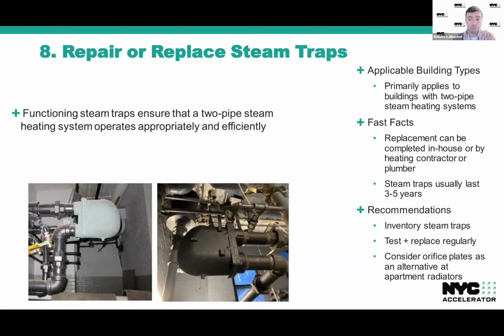This is going to primarily apply to buildings with two-pipe steam heating systems because those have by far the most steam traps. A lot of replacement work can often be done in-house by qualified or competent building staff. Other times, a heating contractor or a plumber is going to be the one who comes in to do this work. Steam traps wear and tear and they break down. A typical steam trap lifetime is approximately 3 to 5 years, which is why it's really important as a general recommendation to inventory steam traps, know where all of the steam traps in the building are, and have a protocol for testing and replacing any broken traps regularly. So staying on top of this, staying ahead of it. And it also might be worthwhile to consider orifice plates as an alternative in apartment radiators, if appropriate, so that you don't need to get into everyone's apartments all the time to do that testing and replacement.